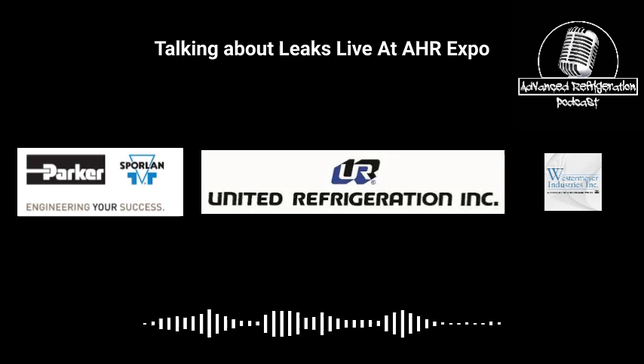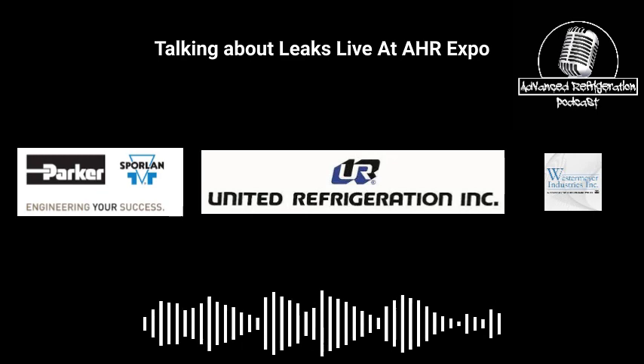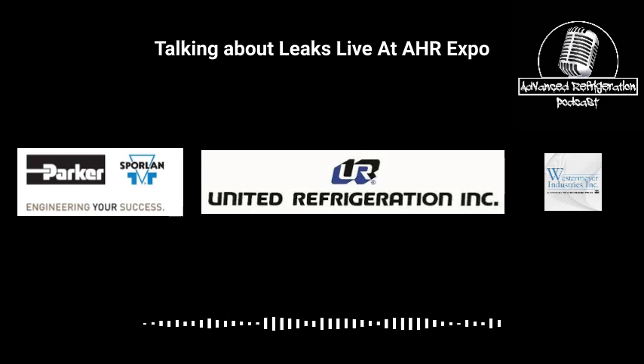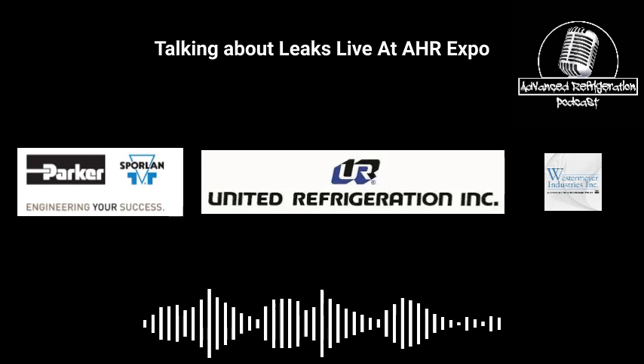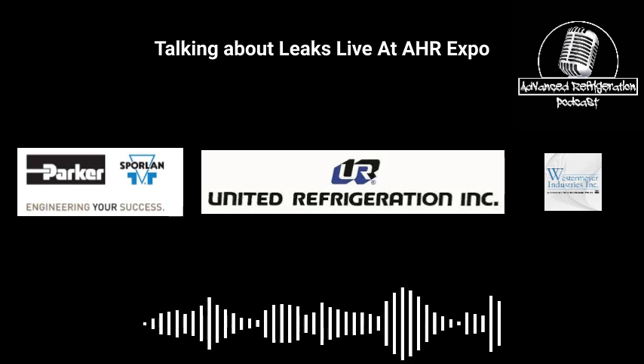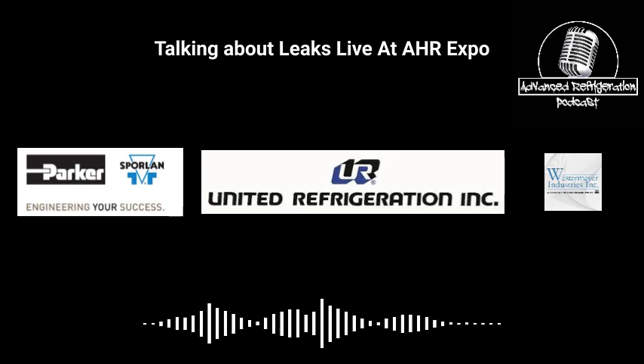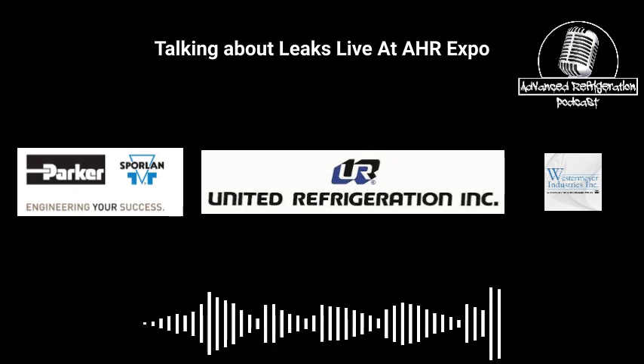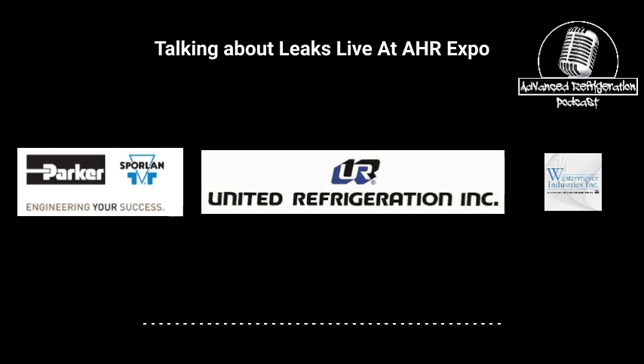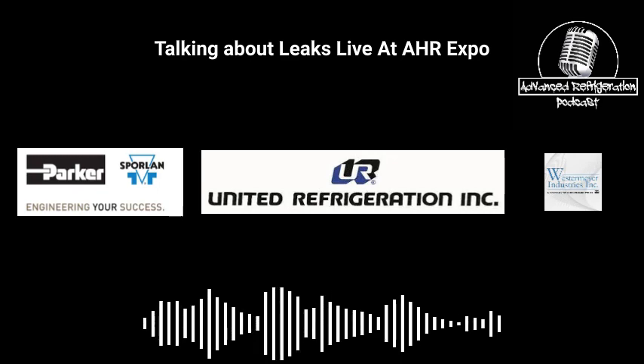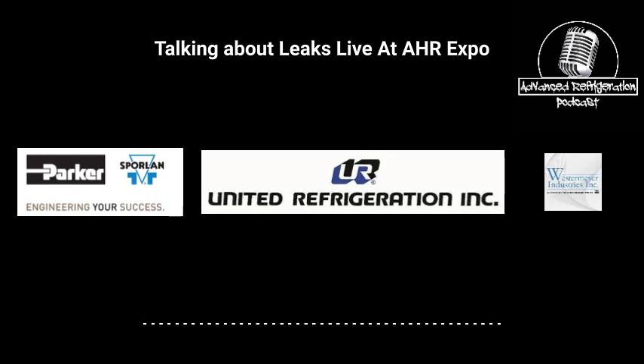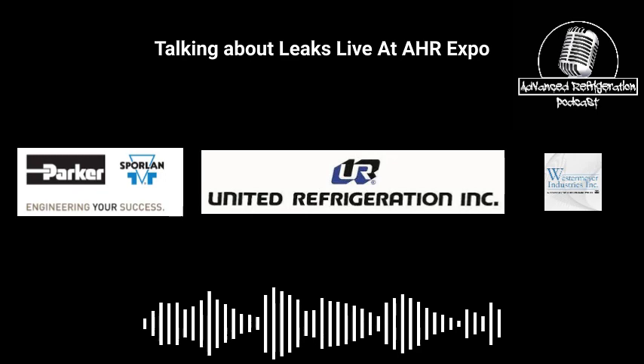Because what happens is after it pops so many times, it gets weak. Especially the discharge reliefs. If a discharge relief went off a bunch of times, it's getting replaced. Usually they reseat, but the discharge reliefs get weaker faster than the reliefs on the flash tank. The flash tank reliefs are usually R410A reliefs, so they're usually readily available at a supply house. So they're a lot cheaper. Those getting replaced, to me, is just cheap insurance. Yeah, agreed, to keep it from popping early or getting weak.